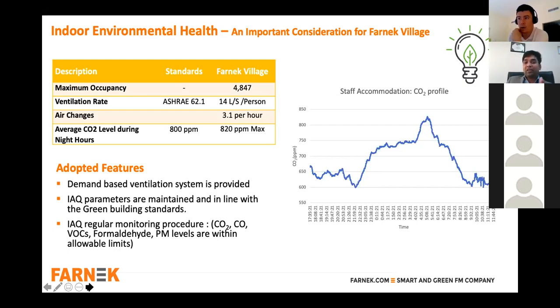Here in the graph, we can see a carbon dioxide profile in the room during nighttime when the room occupancy is maximum. The CO2 levels are mostly well below, more than 90% of the time, the allowable limits of around 800 ppm. This is because of the higher ventilation rates we are providing for the accommodation rooms. I'll explain the importance of higher ventilation rates in line with the ongoing pandemic in the next slide.